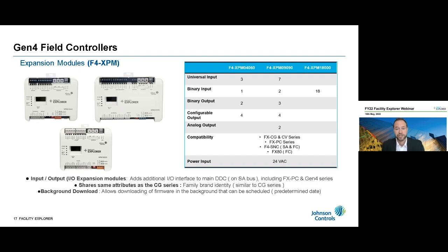Here we wanted to give a refresher on the XPM IO modules, which are used to expand the points for any controller that we have. There are 3 models from the new generation with 10 points, 18 points, and 18 binary input points. The XPMs are connected to the controllers through the SA bus and also support the Gen 4 controller features, such as background download, which allows firmware to update in the background at a predetermined date without disrupting operation.